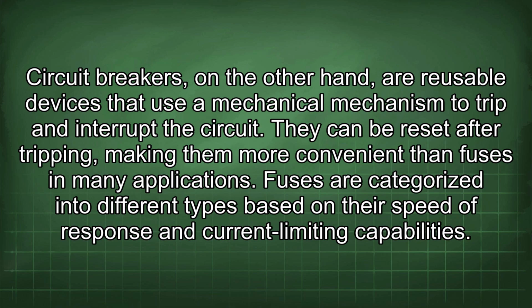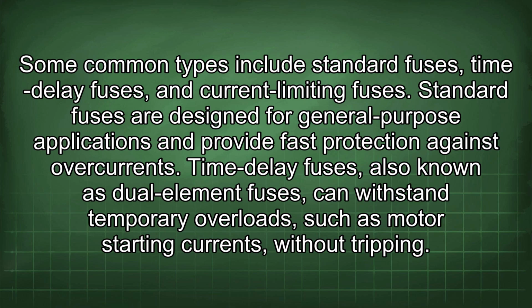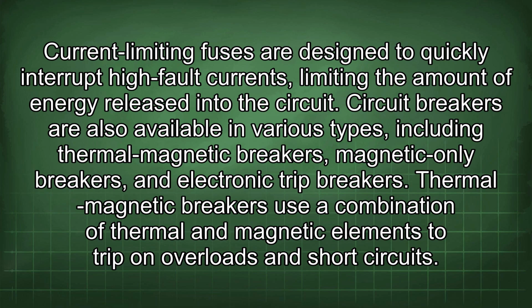Fuses are categorized into different types based on their speed of response and current limiting capabilities. Some common types include standard fuses, time delay fuses, and current limiting fuses. Standard fuses are designed for general-purpose applications and provide fast protection against overcurrents. Time delay fuses, also known as dual-element fuses, can withstand temporary overloads such as motor starting currents without tripping. Current limiting fuses are designed to quickly interrupt high-fault currents, limiting the amount of energy released into the circuit.